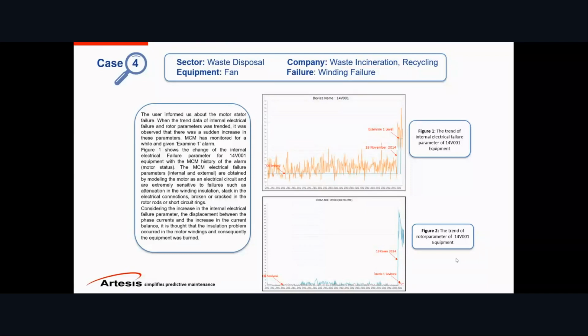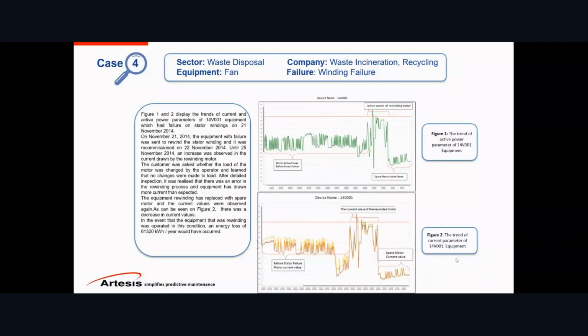So the equipment got burned, and then they sent this motor for rewinding. At first try, when they got the motor back and made it operational, they realized that the currents and the active power under the same load were higher. So there was something wrong here, and we were consulted.